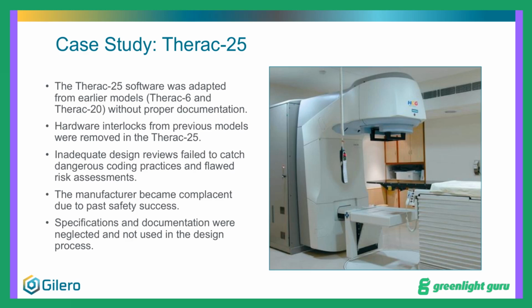The manufacturer believed that because they thus far had a strong safety record, no new significant risks were introduced with the Therac 25 model. Failure to conduct a design review led to failure to catch the impact of the removal of the interlocks, as well as failure to identify poor coding practices, such as failing to sanitize and validate user input variables. Specifications and documentation were viewed as an afterthought throughout the design process in the Therac 25, as well as in the previous models, leading to late documentation with limited coverage that was not used to assess and inform the design process. Why was this the case?